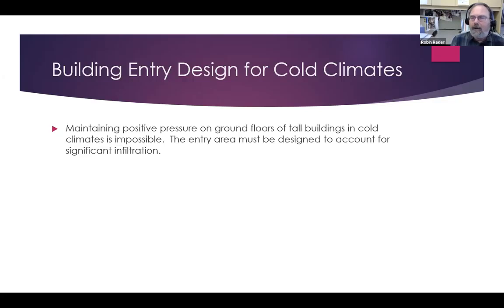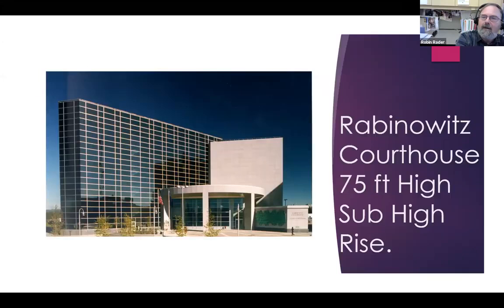So you see people doing things like putting saran wrap over the sprinkler or the roof drains and things like that. So at cold temperatures, trying to maintain positive pressure in buildings is very difficult.